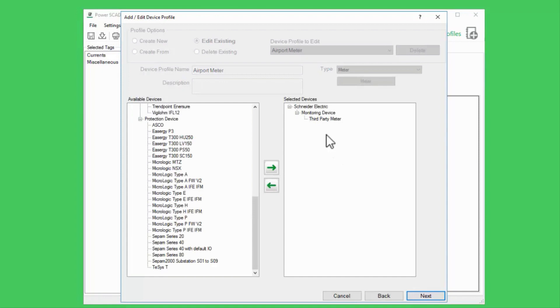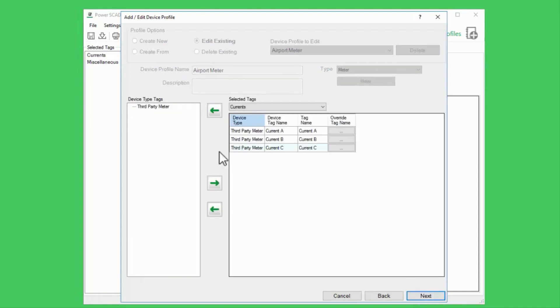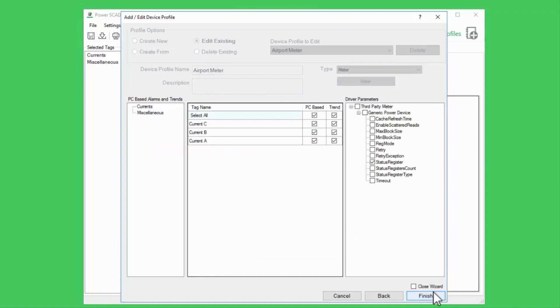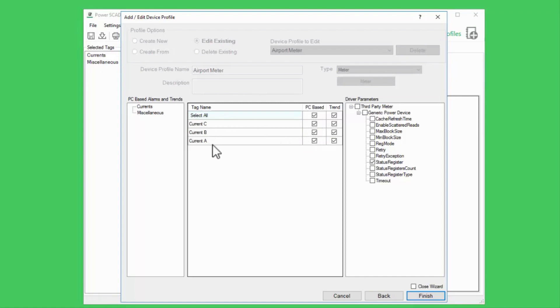I've selected all my tags, which is fine. This page is where I actually create the PC-based alarms. I have PC-based checked for all of my currents in the project's database. Because these are analog variable tags, the alarms will be created as analog alarms. This is important to remember because, as we'll see in the next video, analog alarms have their own set of unique parameters.